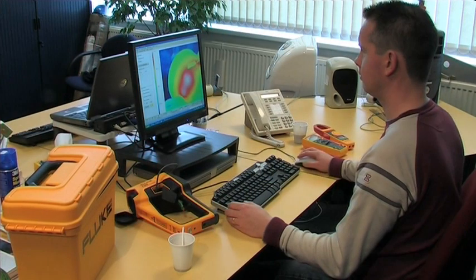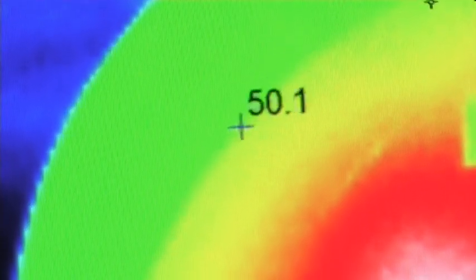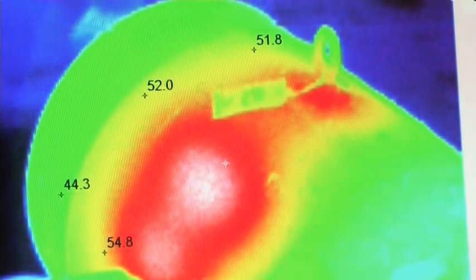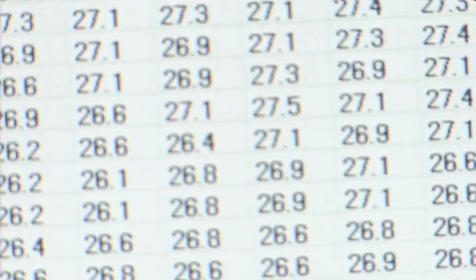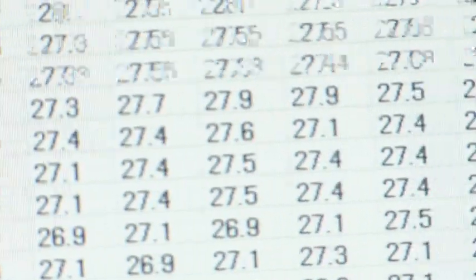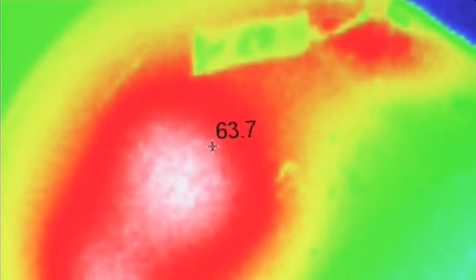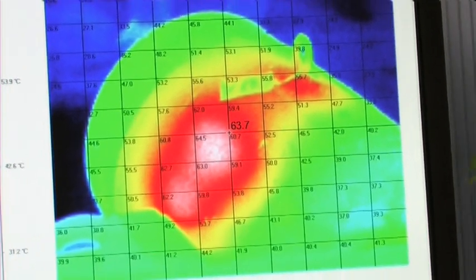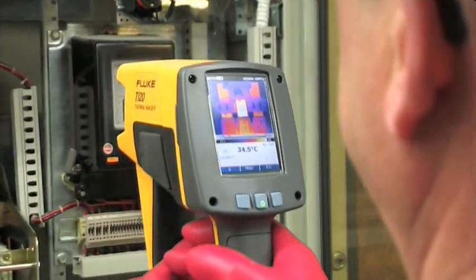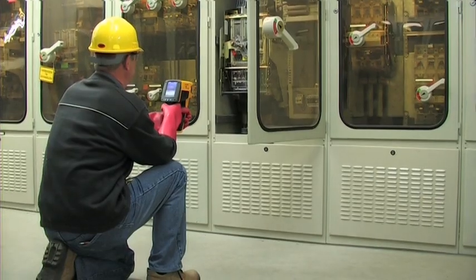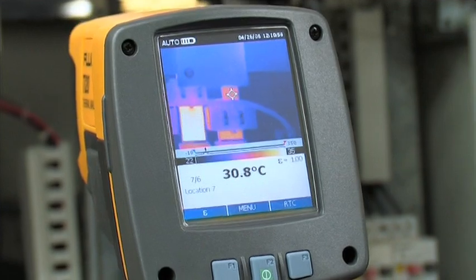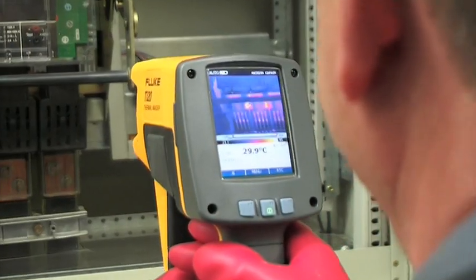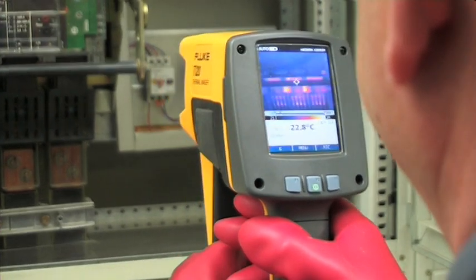For example, if you're using an imager with 160 by 120 resolution, it gives you 19,200 pixels. Because it's fully radiometric, every one of those 19,200 pixels is stored with a temperature measurement. All these data points can be recalled to disclose the exact temperature of the area of interest and be used for detailed image analysis or trend analysis of multiple images over time. That's what makes fully radiometric thermal imagers such a powerful predictive maintenance tool. All Fluke thermal imagers are fully radiometric, making them excellent for finding potential problems before they cause actual failure.